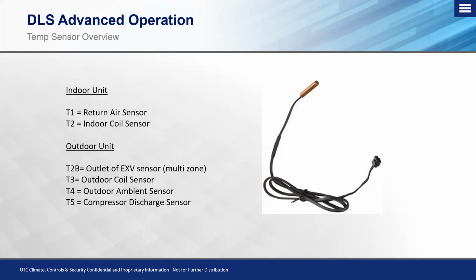But this sensor essentially is what's going to govern that, and the whole reasoning behind it is so that as soon as the system has a call for heat, we're not blowing cold air on the customer. When the fan starts running is when that warm air is going to be coming out, satisfying that. And of course, the T1 sensor on there is going to be measuring room air to make sure that we're not overheating and that we're not overcooling the space, and we're meeting exactly what the customer wants out of that system.